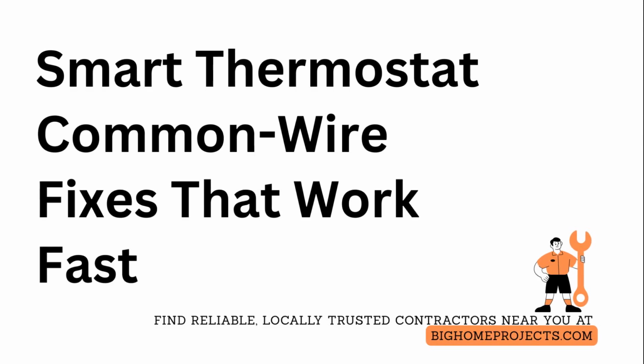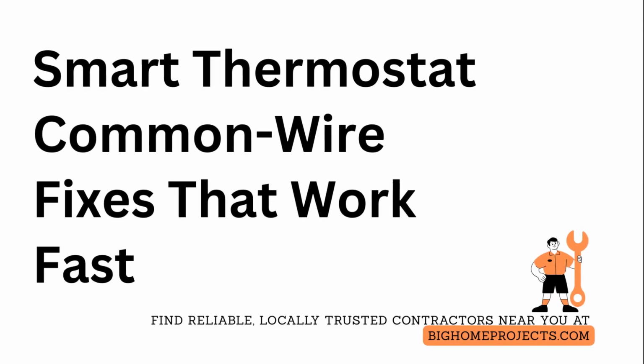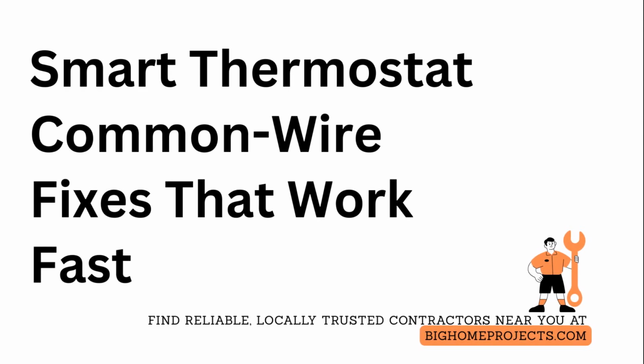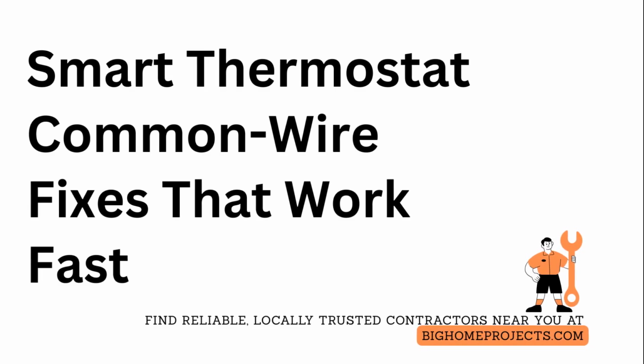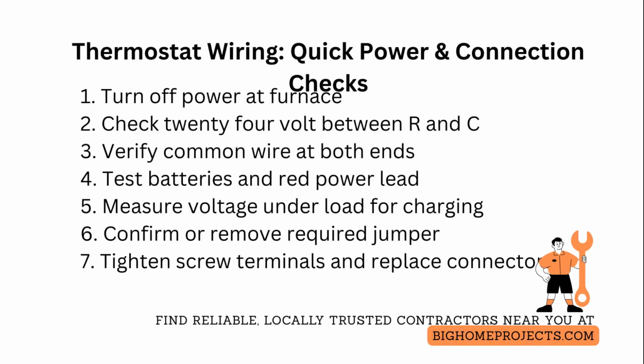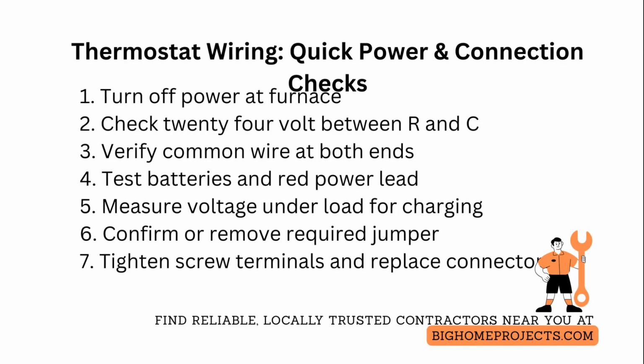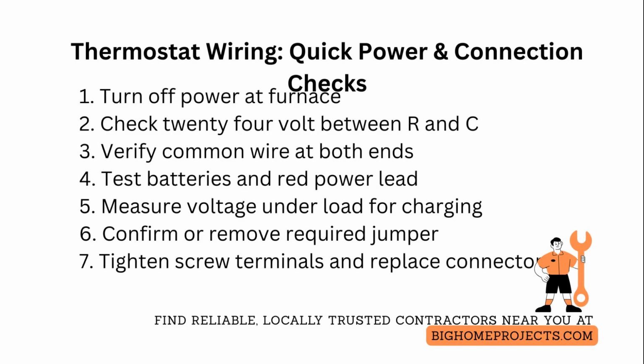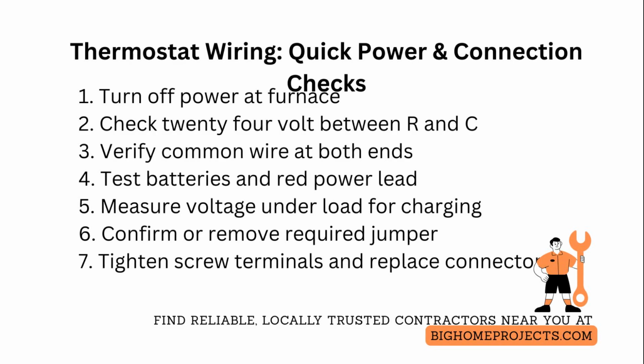If your thermostat is unresponsive after wiring, quickly verify power and connections so you don't leave your heating or cooling system offline. Start by turning off power at the furnace or air handler to avoid shorts. Then remove the thermostat cover and check for 24 volt between the red and common terminals with a multimeter. If you do not see 24 volt, trace back to the transformer at the control board and verify the transformer secondary output is present and not grounded.